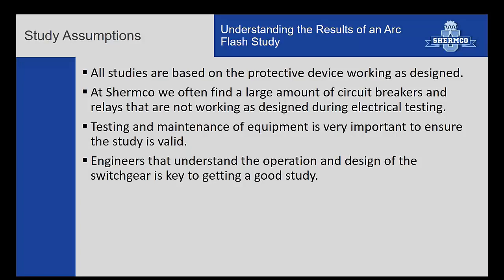Okay, would you have to run an arc flash study with the maintenance mode scenario in the ETAP or SKM or EDSA software? Yes, you would definitely have to run it in both settings. And then my preference would be that you label the gear without the maintenance mode on, with the higher settings. And then you're clearly making your procedures: if you turn this switch and you're doing these tasks, it's lowered to this.